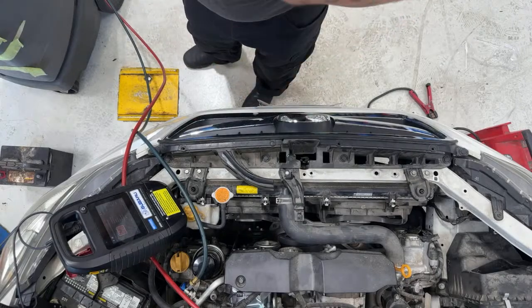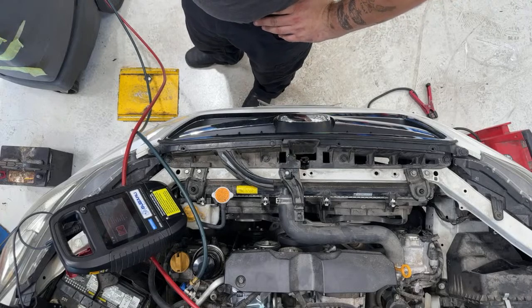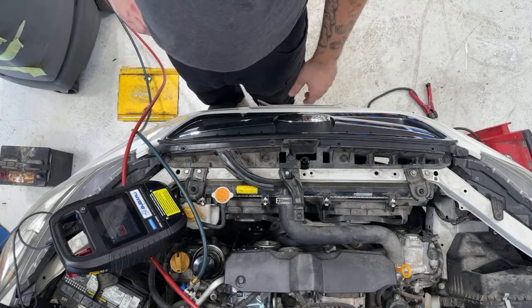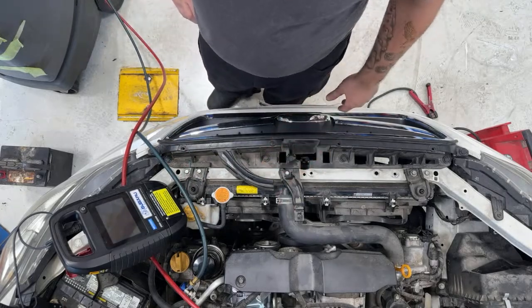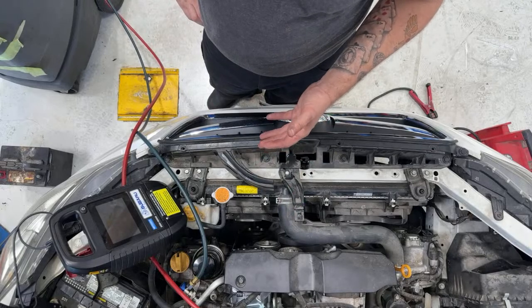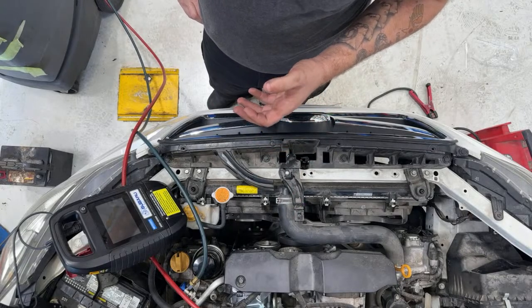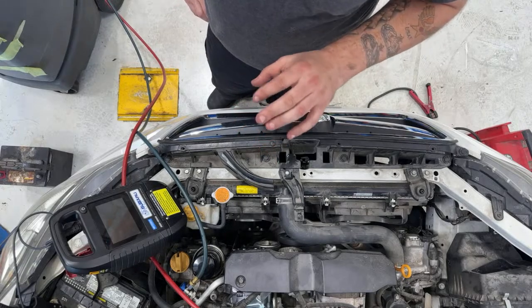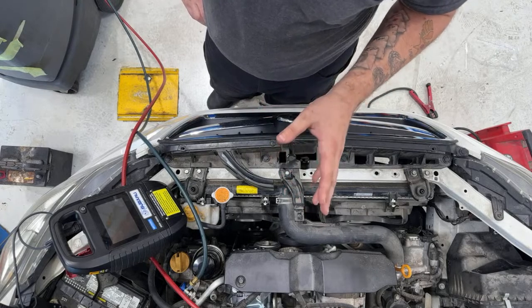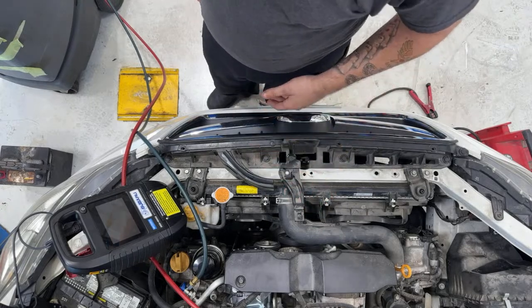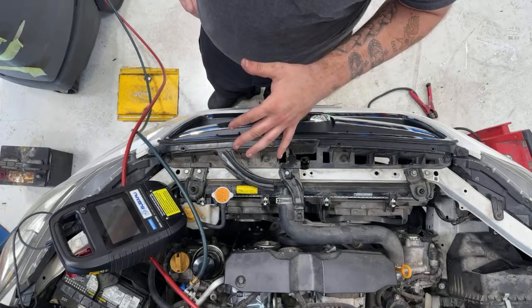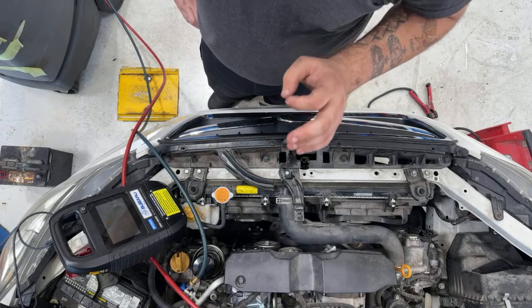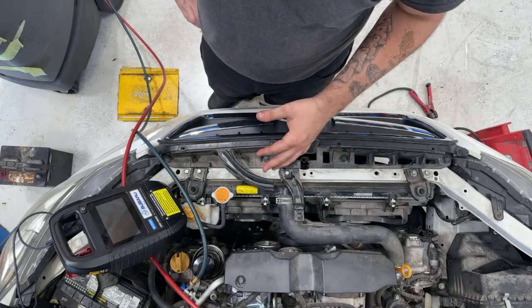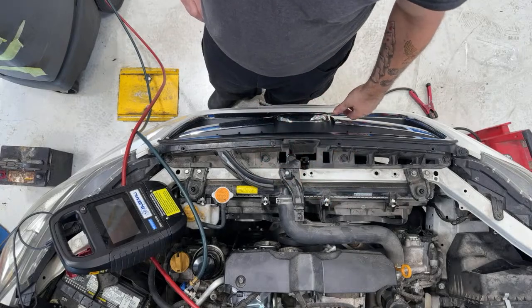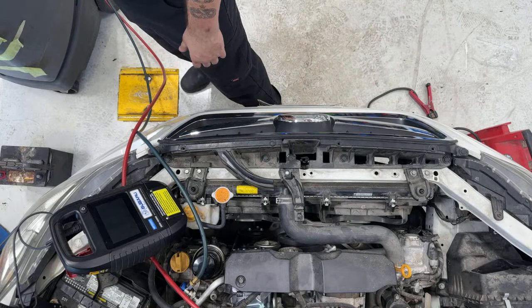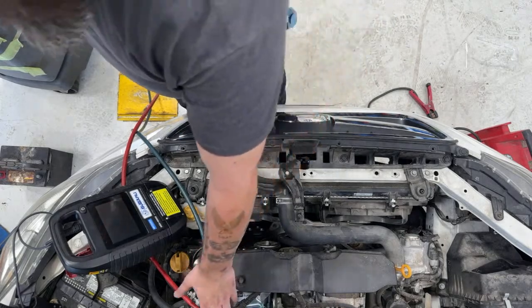Okay, so I'm going to do something based on my experience. I already saw a lot of oil drip out of these lines. I'm willing to bet there's a ton of oil in this system, and I am not about to introduce any more. If I hear the compressor make any kind of noise, I'll shut down the system immediately. You can turn your system on, and if you hear something you don't like, turn it off, then put oil in. I'd rather do that than overcharge this thing with oil, because systems overcharged with oil take forever to clean out — I've had to do evacs and recharge like 10 times trying to pump all the oil out of a system. I'll be injecting all my Freon through the high side.